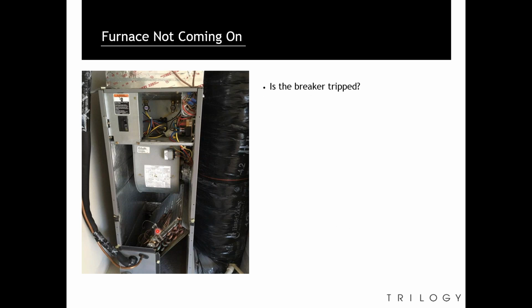Is the breaker tripped? Check and make sure the breaker isn't tripped and we have 240 volts coming in. Is the fuse blown? Make sure the fuse is not blown. If it's blowing, check your low voltage wire. Chances are they're touching and that's creating that blown fuse. Is the transformer working properly? If we have 240 volts, we may need to test the transformer to make sure it's sending the correct voltage to the fan control board. To test that, simply put your leads on the common and the 230 terminal when you ground yourself out.